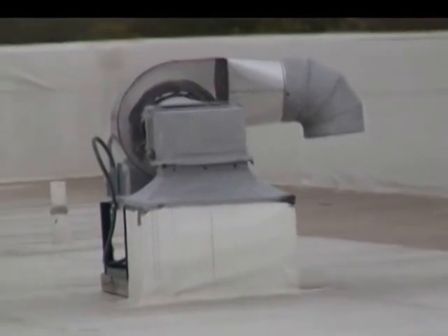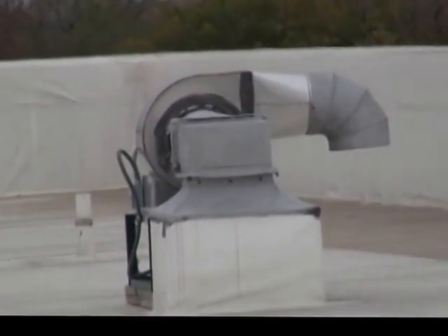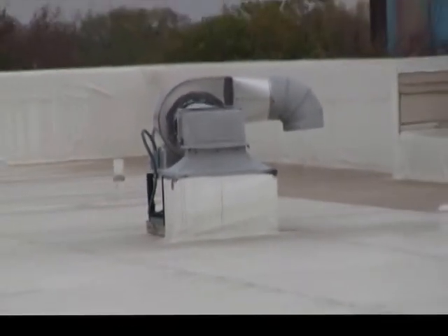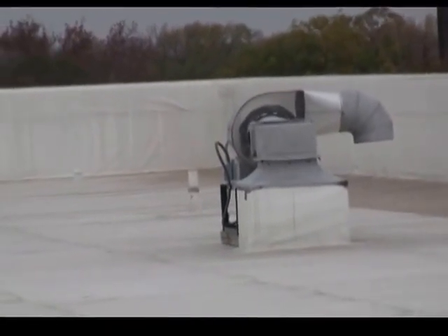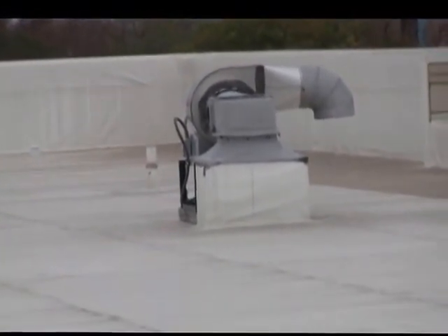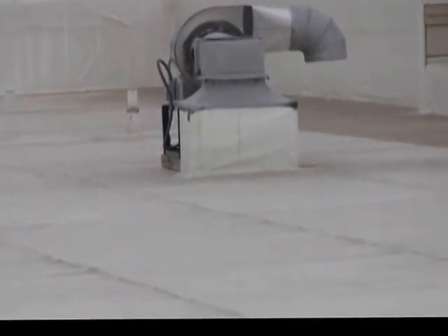Down the line here, straight up from the laundry room, there's a Cyclone exhauster, which is tied into the dryers in the basement, runs off negative pressure. It idles continuously at very low RPM, and whenever dryers are brought online, the static pressure changes in the duct system and it increases speed.